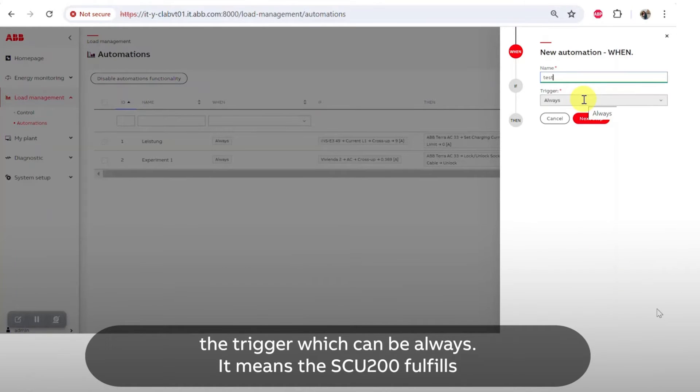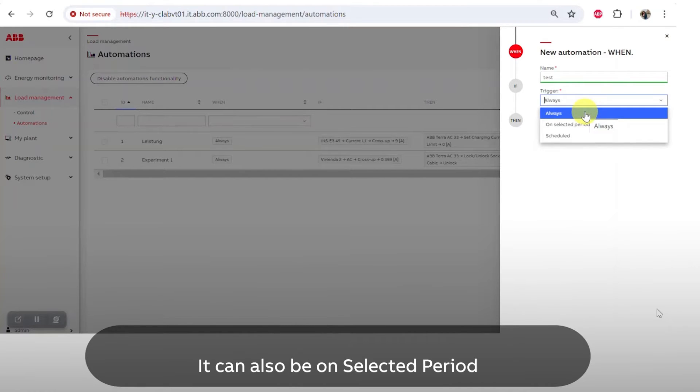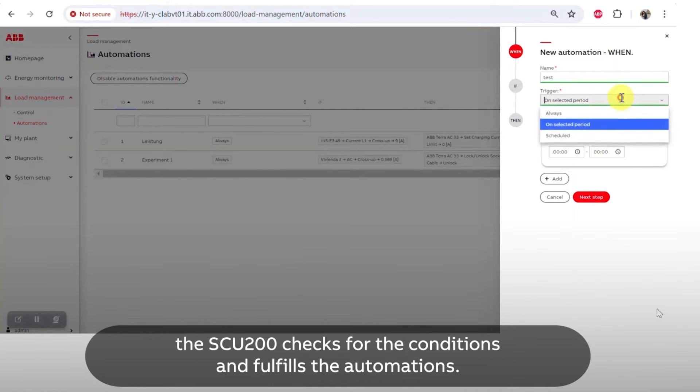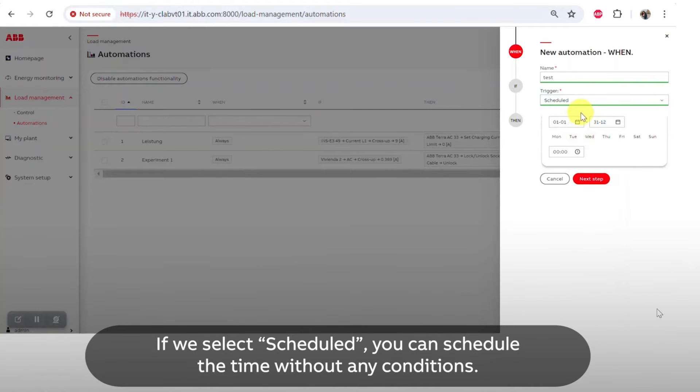The trigger can be always, which means the SCU200 fulfills the automation whenever the conditions are met. It can also be on selected period, where the SCU200 checks for the conditions and fulfills the automations during selected periods. If we select scheduled, you can schedule the time without any conditions for the automations to happen.